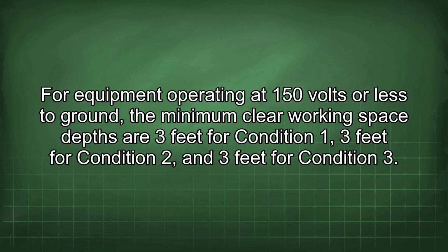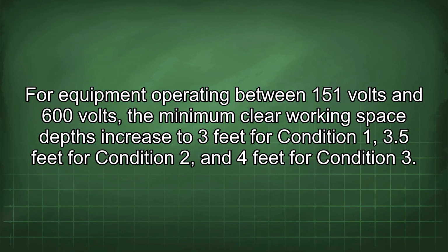For equipment operating at 150 volts or less to ground, the minimum clear working space depths are 3 feet for condition 1, 3 feet for condition 2, and 3 feet for condition 3. For equipment operating between 151 volts and 600 volts, the minimum clear working space depths increase to 3 feet for condition 1, 3.5 feet for condition 2, and 4 feet for condition 3.